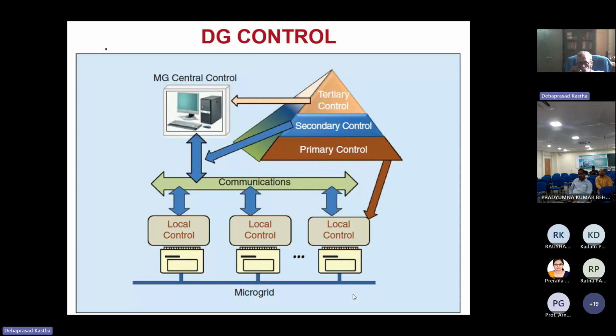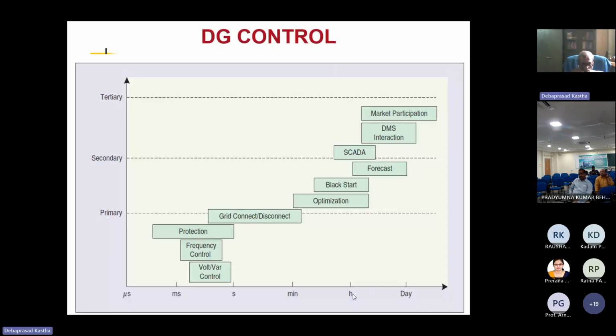This is called hierarchical control. There are three levels. You have the DGs with their local controllers, and then you have primary control, secondary control, and tertiary control. What are the functions of this control? In the primary control, you have voltage or VAR control, frequency control, protection, grid connect, disconnect. These are mostly the primary control and generally done faster. In the secondary control, you have optimization, that is, you have to optimize the resources of the DG.